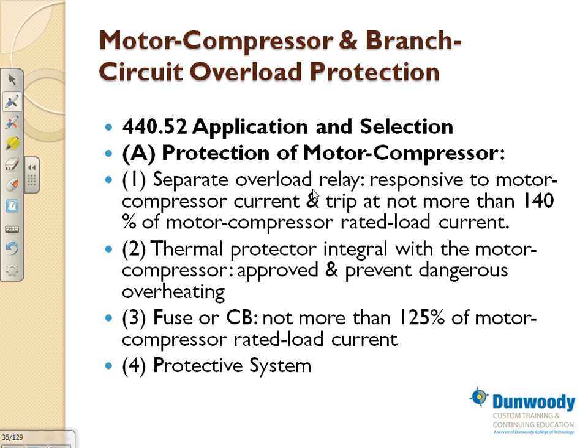Overload protection, there are a few things about overload protection. You can have a separate overload relay, and if you look at that, you can size it at not more than the value they use for HVAC equipment. Most of the time, guys, the HVAC equipment comes with its own controller overload protection. Electrically speaking, we don't mess with it. We might provide a fuse disconnect right next to them, or we just provide a power feed, which is a circuit breaker with a feeder tied to their disconnect that's already on the equipment.